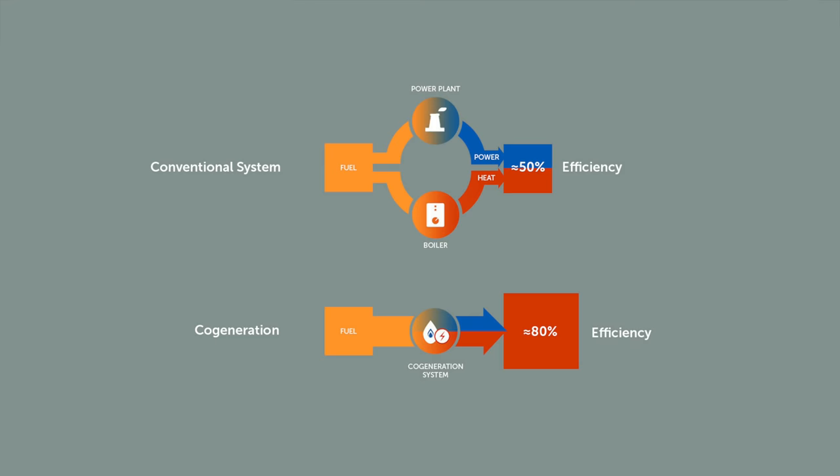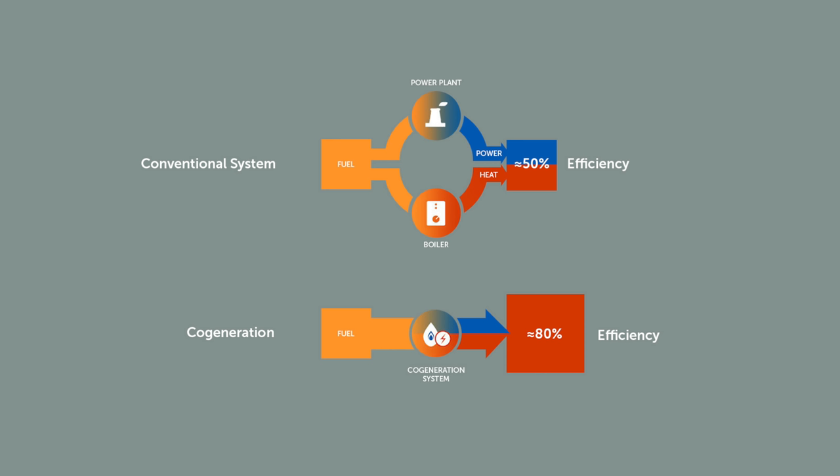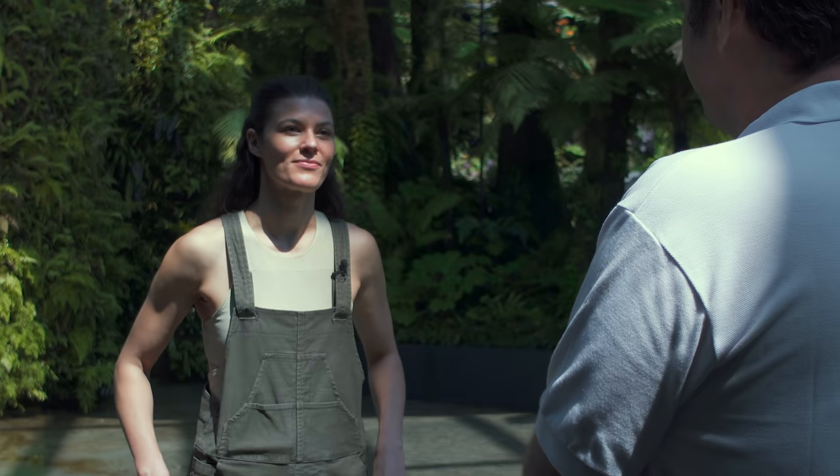So is that like a biofuel? It's called a biofurnace and a co-gen power plant. We burn the waste and use it a few different ways. It makes enough electricity to cool the conservatories, and then there's heat left over with a heat exchange system that drives the chillers in the floor. They also came up with a liquid desiccant system that dries the air before it goes into the chillers. Here in Singapore, where it's 95% humidity 95% of the time, it increases the efficiency of the chillers by about 10%, and that system will pay for itself over time.